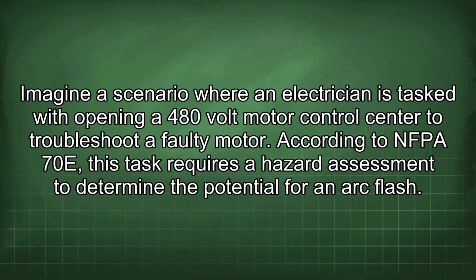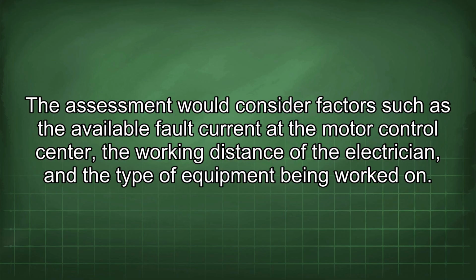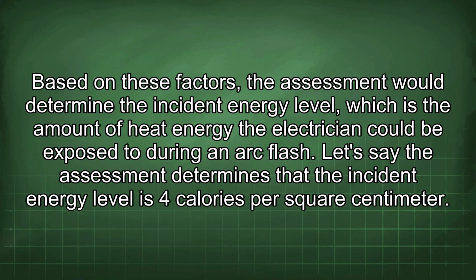Imagine a scenario where an electrician is tasked with opening a 480-volt motor control center to troubleshoot a faulty motor. According to NFPA 70E, this task requires a hazard assessment to determine the potential for an arc flash. The assessment would consider factors such as the available fault current at the motor control center, the working distance of the electrician, and the type of equipment being worked on. Based on these factors, the assessment would determine the incident energy level, which is the amount of heat energy the electrician could be exposed to during an arc flash.